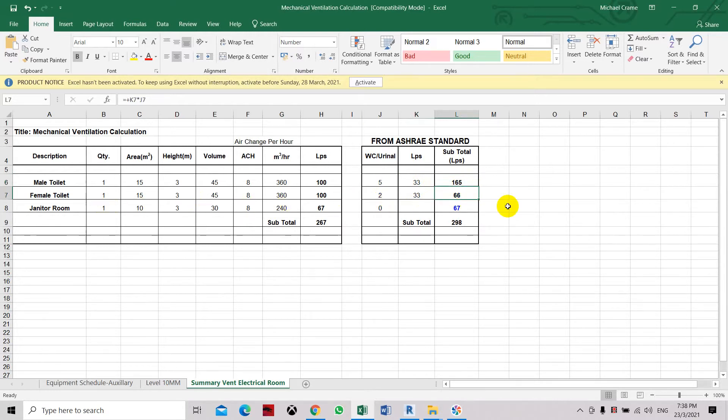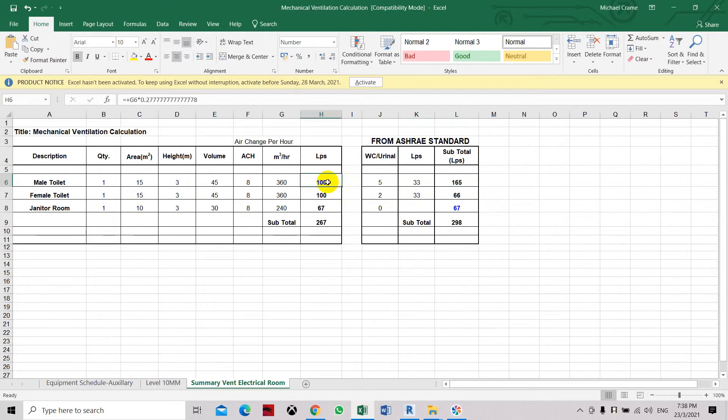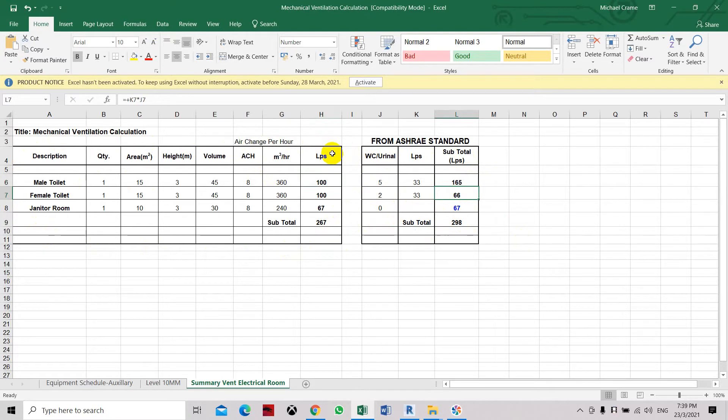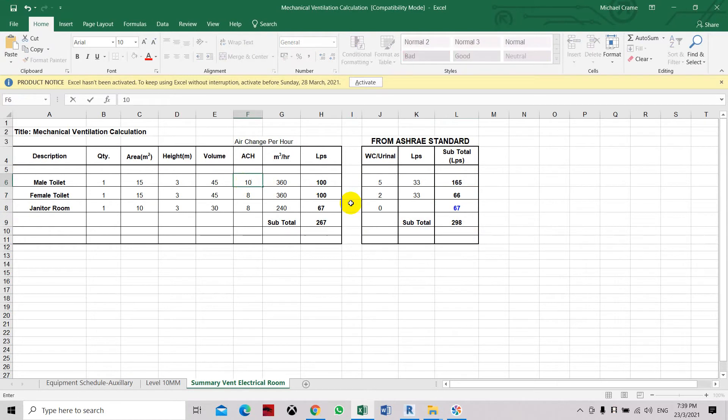And the female toilet will require less because it has less fixtures or plumbing fixtures inside the area. So this male toilet, the ventilation capacity is higher than the female toilet based on the ASHRAE standard. So typically I will follow this ASHRAE standard. The air change method is used if you have any special client requirements who need a high exhaust air flow.